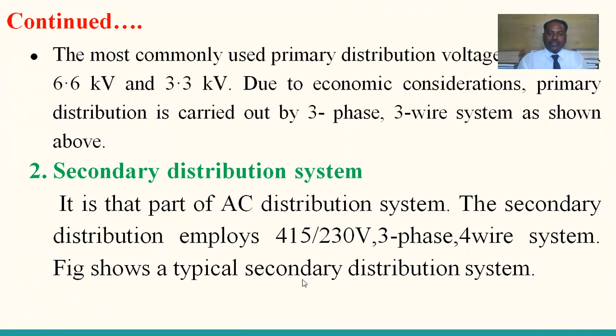So this is the typical diagram of the secondary distribution system, where we have an 11 kV, 3-phase delta-star distribution transformer. The primary side is delta and the secondary side is star. So there are three-phase 4-wires, that means three phases R, Y, B along with neutral.